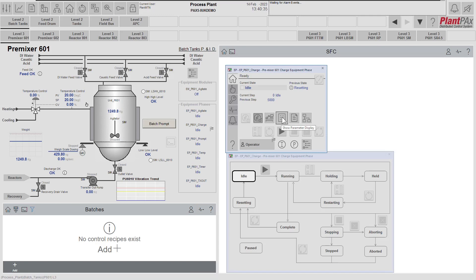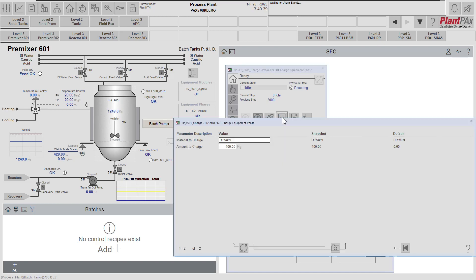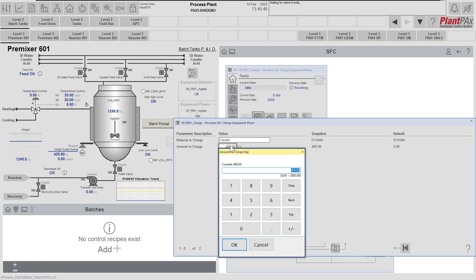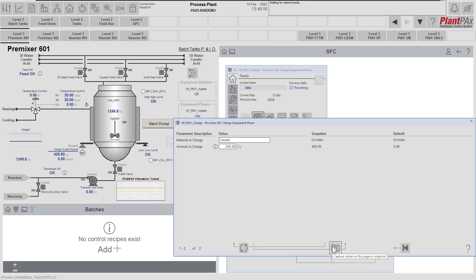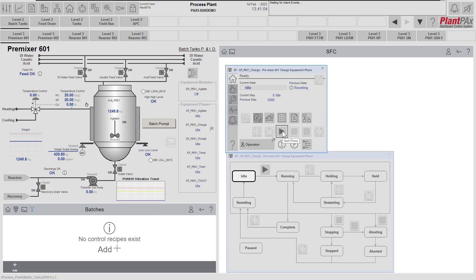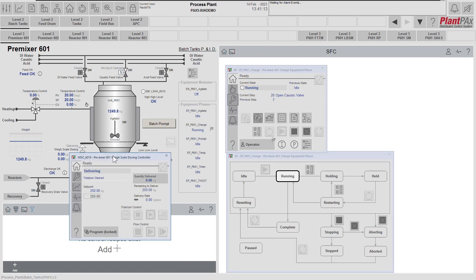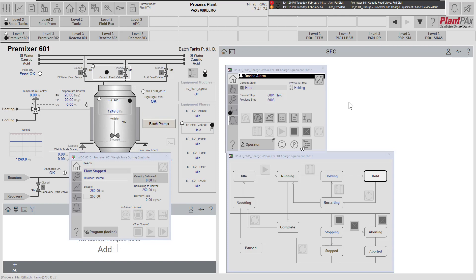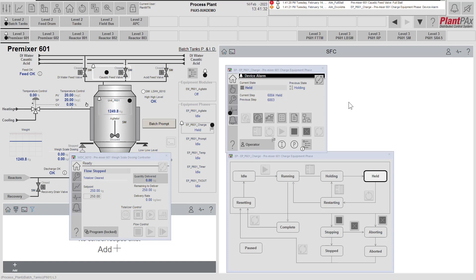I'll switch back to our PlantPAx operator workstation and set up to do a caustic charge using the charge equipment phase. Let's go into our phase parameters and set it to do a caustic charge — this time we'll ask for 250 kilograms. We'll load that into the snapshot and then ask the charge phase to run. Notice that it goes straight into running since we've already acquired the devices. It set up the weigh scale dosing controller with our 250 kilogram set point and now it's trying to open the caustic feed valve, which did not open because of the fault we set up in Emulate 3D — and that has caused a device alarm.